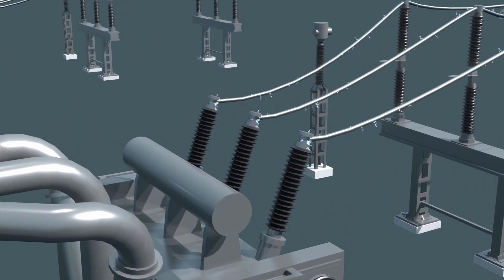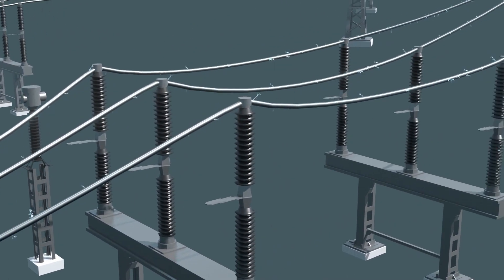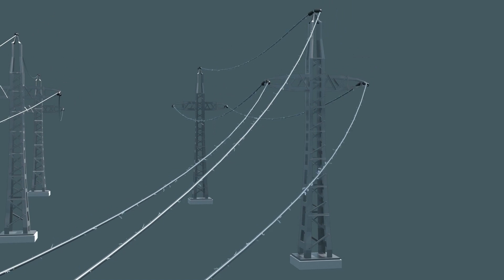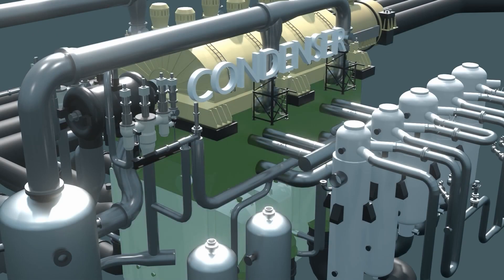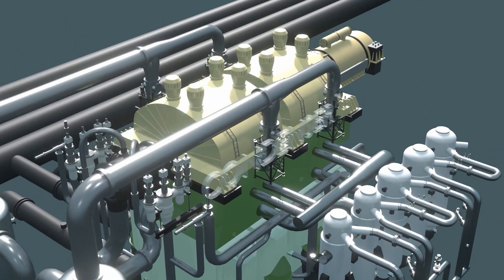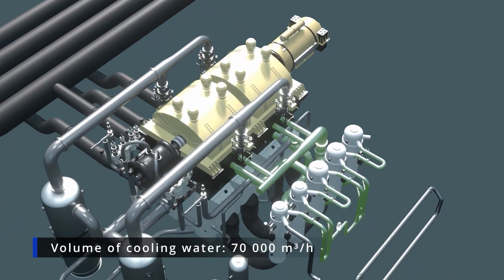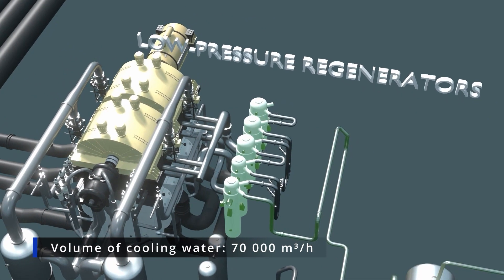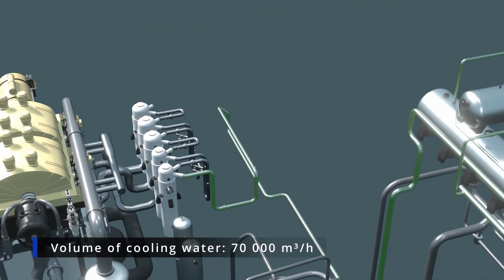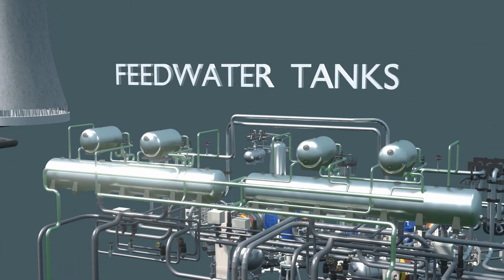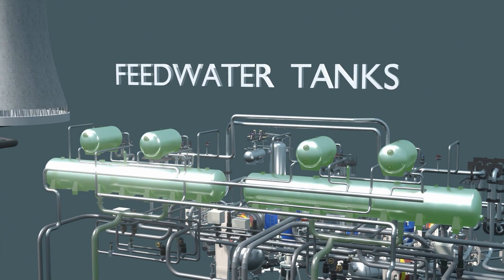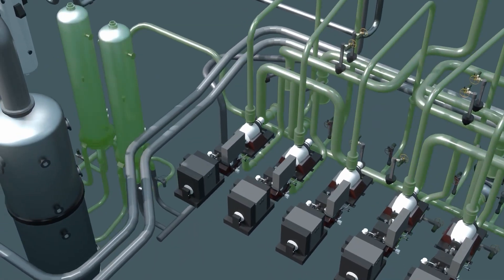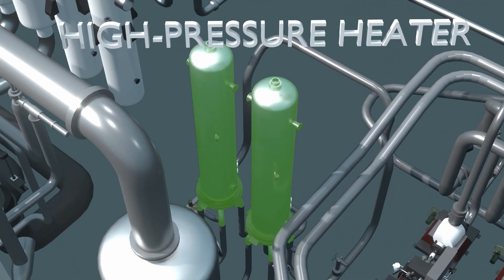While the electricity from the nuclear power plant is already on its way to you, the steam of the secondary circuit is condensed in a condenser after passing through the turbine. It is converted back into water and passes through the low-pressure regenerative heaters to the feed tank, and from there through the high-pressure heaters back to the steam generators, thus closing the secondary cooling circuit.